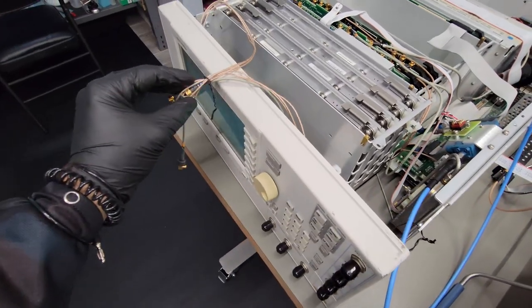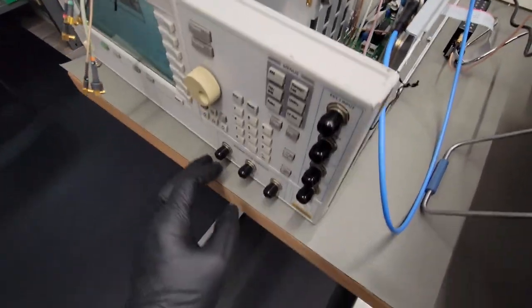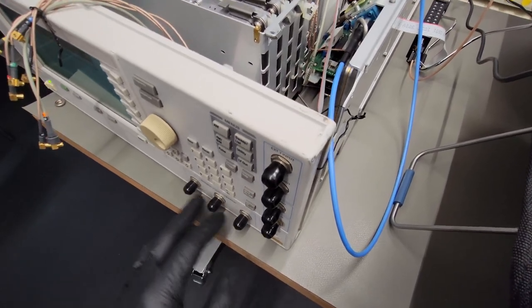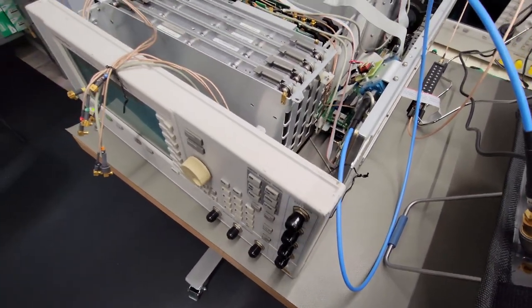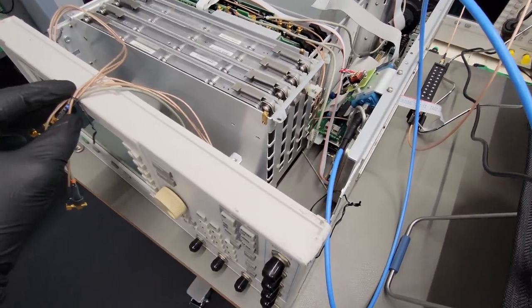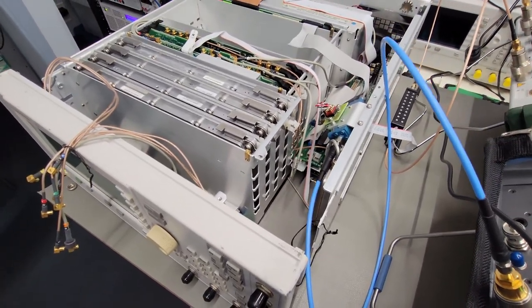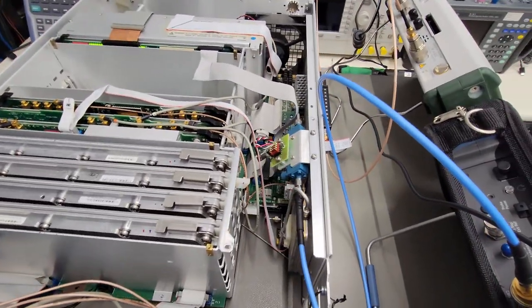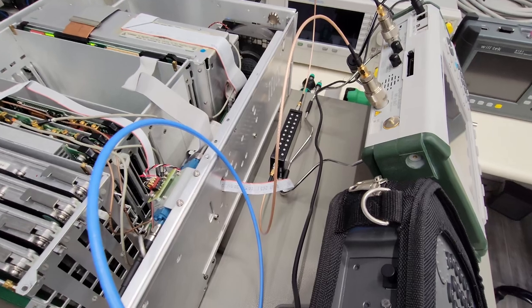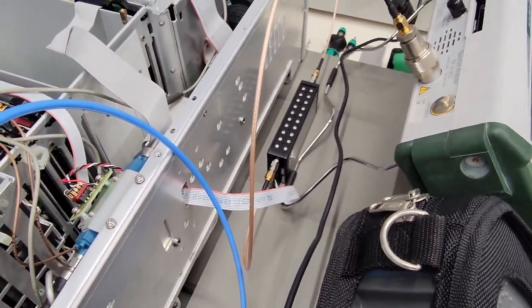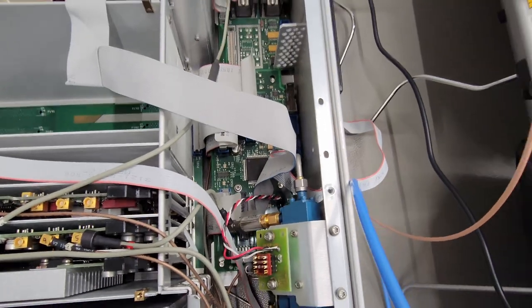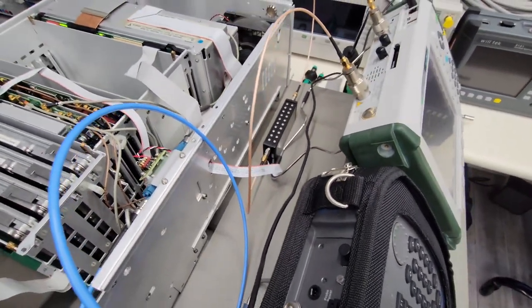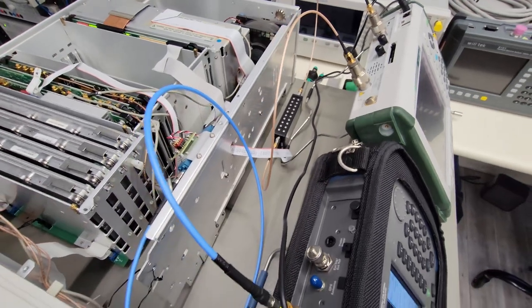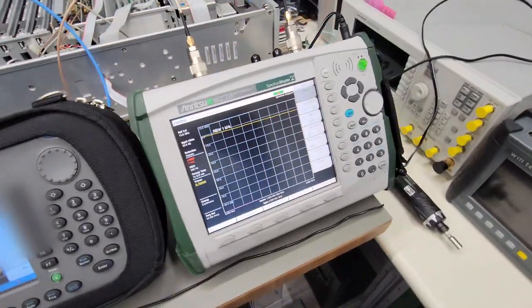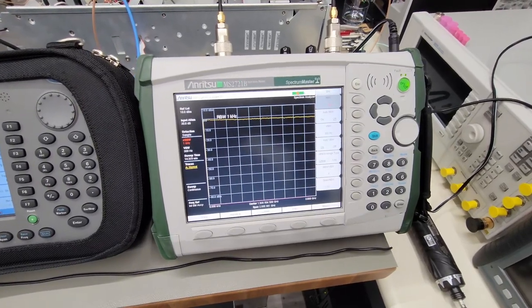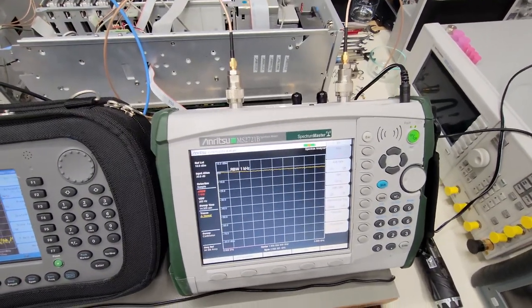We don't need any of these coax cables connected. These are all of the BNCs on the front for different inputs and ALC, and you have the pulse generator connections here. So we don't need that just to do the testing that we need to do to troubleshoot. And you can see the attenuator is out of the instrument, but the attenuator control voltages are still connected. So it's still connected internally to the mid deck here. And what this can allow me to do is test the attenuator outside of the instrument with a separate device. And for that, I'm using this Anritsu MS2721B because it has an internal tracking generator.